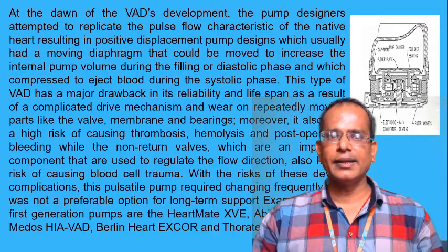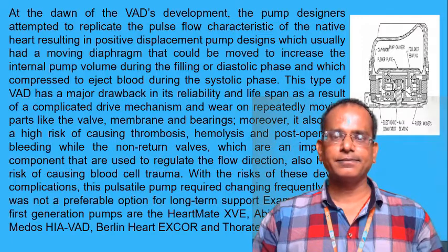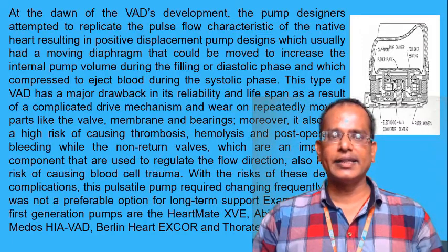These types of VAD had major drawbacks in reliability and lifespan as a result of the complicated drive mechanism and reliance on repeatedly moving parts like valves, membranes and bearings. Moreover, they also had a high risk of causing thrombosis, hemolysis and post-operative complications, and also a risk of causing blood cell trauma.